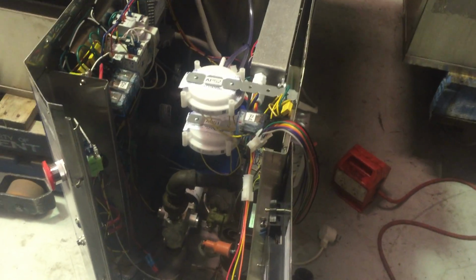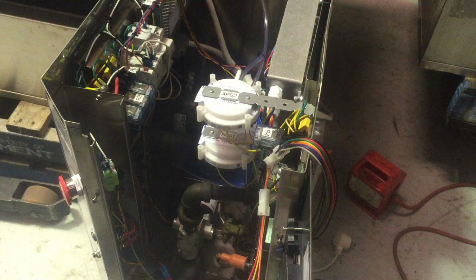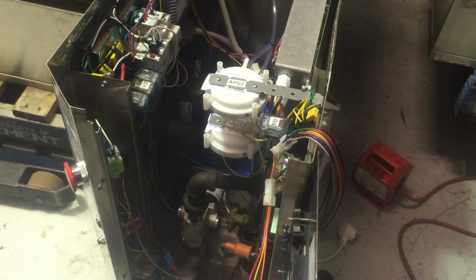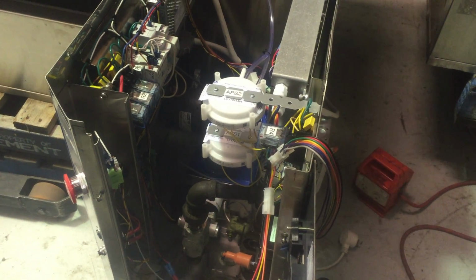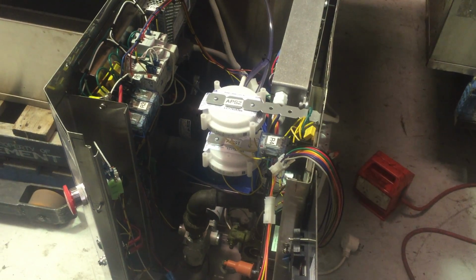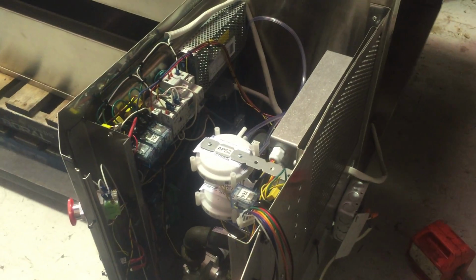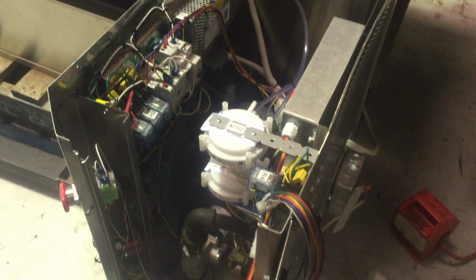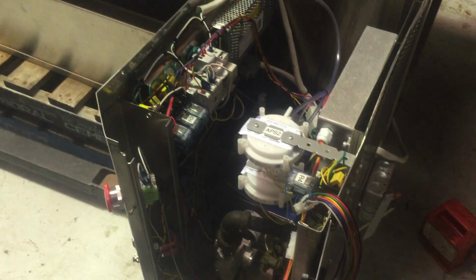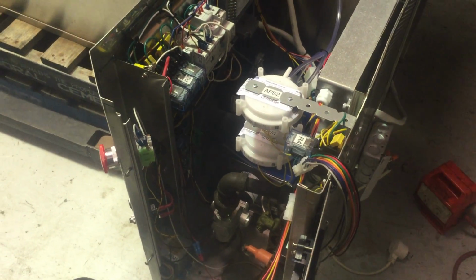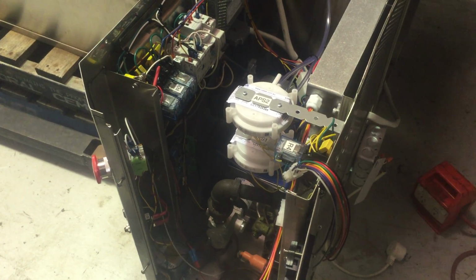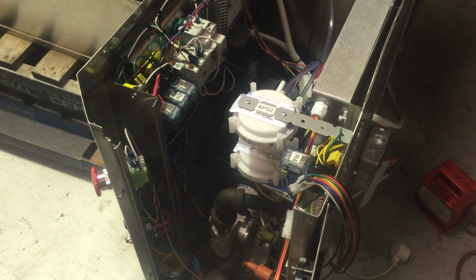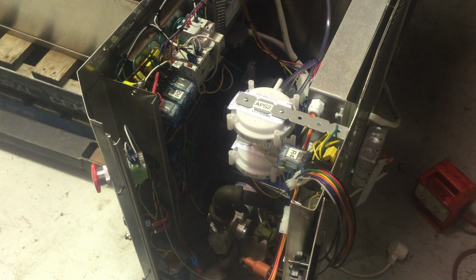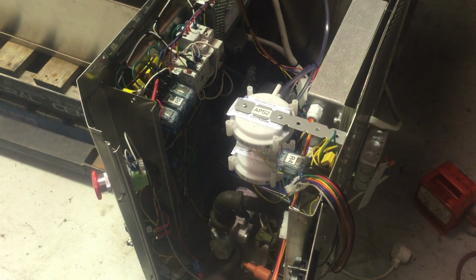Beautiful. So a couple of safety things there - we've got a high limit, a mechanical high limit in this now, whereas the old ovens didn't have that system. And the significance of that is: if the solenoid fails open or there's a fault with the temperature sensors, the high limit will take out the burner and shut it down, so that we're not going to get too hot.